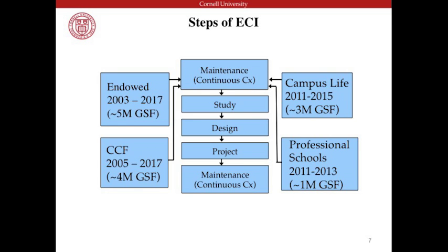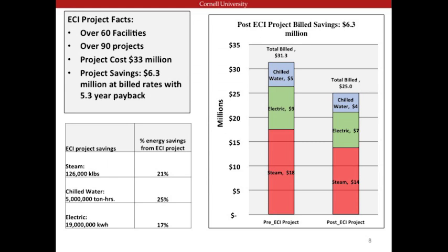We just finished up the project about last year, and 6 to 8 months after completion we evaluated the energy savings. We did a weather regression on how the building was operating compared to pre-project, and found some great savings. We had an original $4 to $5 million target goal, and ended up with $6.3 million of energy reduction, a 5.3-year payback, on the $33 million the university allowed me to spend. We were able to reduce steam use by 21%, chilled water by 25%, and electricity by 17% in the buildings where we did projects.